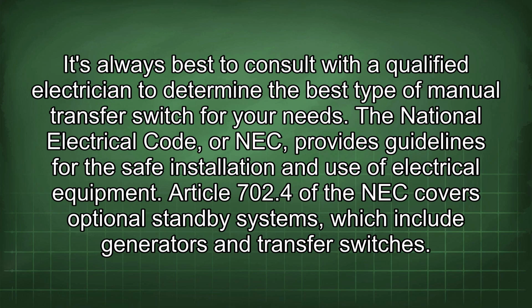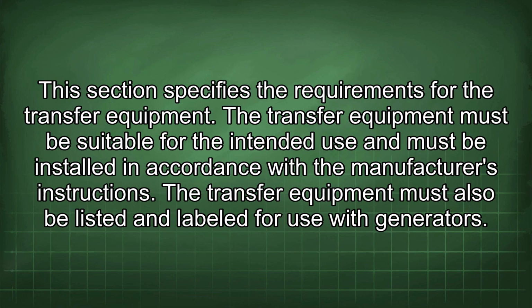Article 702.4 of the NEC covers optional standby systems, which include generators and transfer switches. This section specifies the requirements for the transfer equipment. The transfer equipment must be suitable for the intended use and must be installed in accordance with the manufacturer's instructions. The transfer equipment must also be listed and labeled for use with generators.